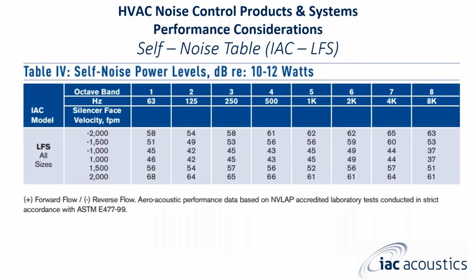Another table is the self noise levels. We like to showcase this. If there's any given time at a face velocity in feet per minute, say 720 or negative 860, let me know and I can send you some tables. We have some really nice tables that we can share, so you can see this firsthand. At the same time, going into the virtual tool, you can plug in the width by height by length, plug in the CFM, and pick a silencer. It gives you the dynamic insertion loss and the self noise levels.